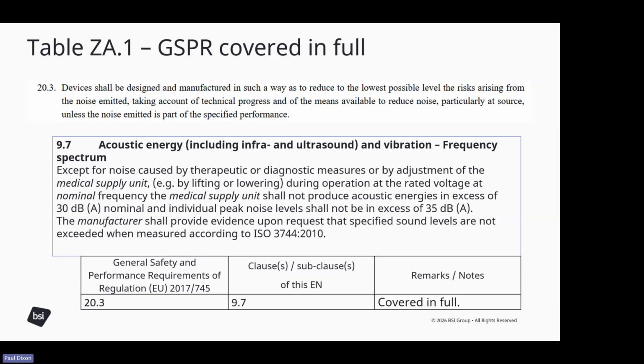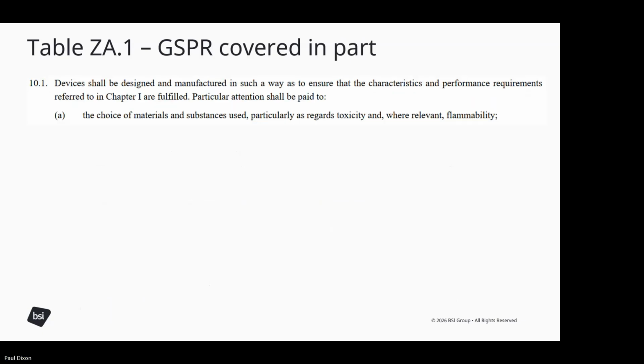The GSPR is simply listed by number in the left-hand column. The clause or clauses of the European standard, the international standard, it's clause 9.7, and in this case, the remark would simply be covered in full, or to be honest, if it is covered in full, you can leave the remark empty. More commonly, you'll have a GSPR that's covered in part. For example, 10.1: devices should be designed and manufactured in such a way as to ensure characteristics and performance requirements are fulfilled, particularly as regards toxicity and, where relevant, flammability.